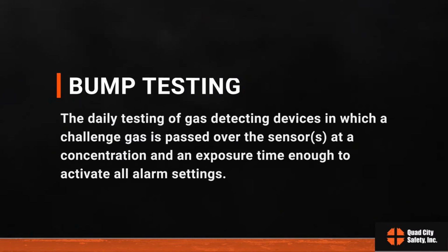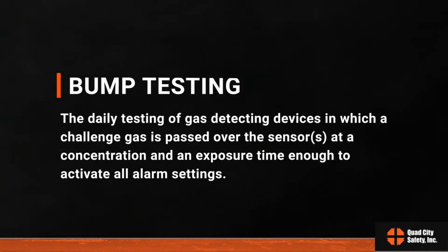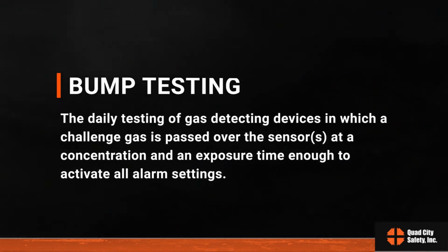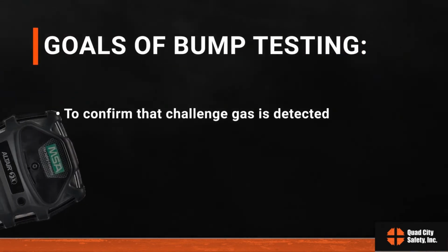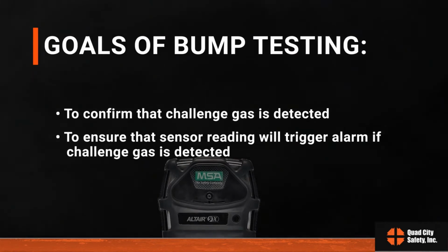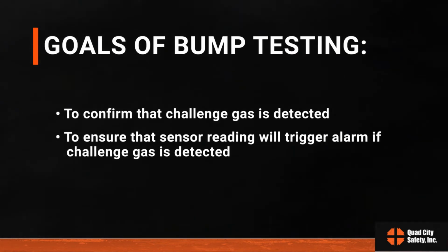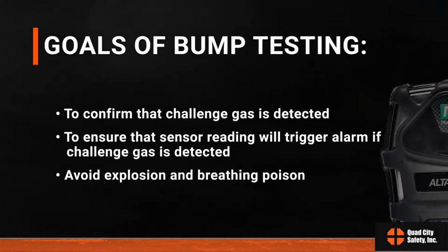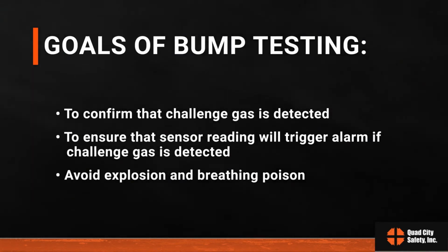Finally, to be sure your devices work, you need a bump test. Bump testing is the daily testing of gas detecting devices in which a challenge gas is passed over the sensors at a concentration and an exposure time enough to activate all alarm settings. The goals of bump testing are to confirm that challenge gas is detected, to ensure that sensor readings will trigger an alarm if challenge gas is detected, and to avoid explosion and breathing poison. That's kind of a big deal.